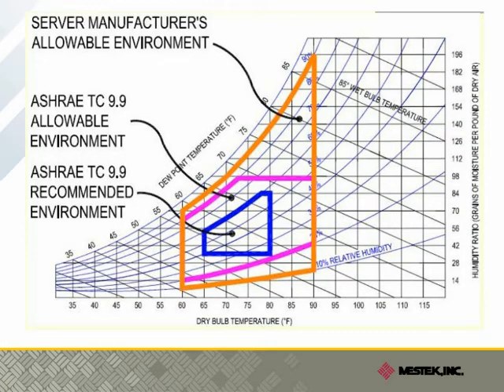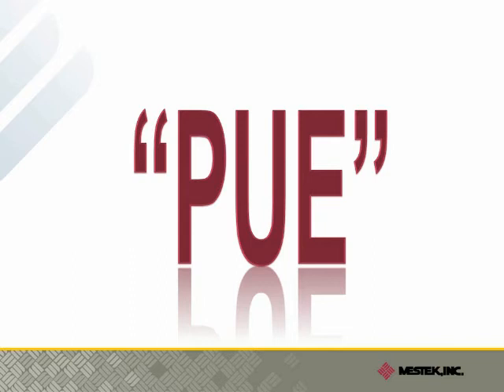The reason this is now a viable alternative to conventional cooling solutions is that the world of server design has changed. Server manufacturers publish data showing that their servers work just fine with inlet temperatures of 90 degrees F — and even higher for the newest state-of-the-art designs — and relative humidities from 10% to 90%. As we look at the application for evaporative cooling in data centers and server rooms, we encounter a term: PUE.